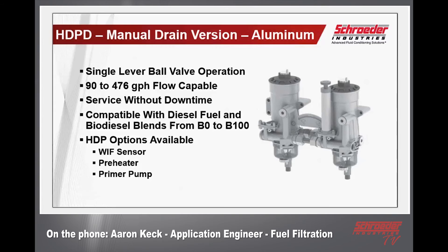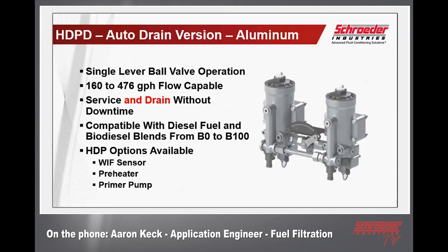The idea is to make it a serviceable filter without downtime or interruption for the diesel engine — you can switch to one housing and service the filter on the other that is out of service. In the case of a manual drain where you're developing water in the sump, you can drain it off while the system operates on the other housing and then switch back. This is compatible not only with diesel fuel but also biodiesel blends from zero to 100 percent blends. The same WIF sensor (water in fuel sensor), flow-through fuel preheaters, and primer pumps available for the HDP are also available on this product — primer pumps available for the 600 manual drain version only.